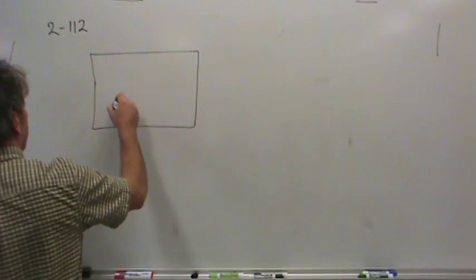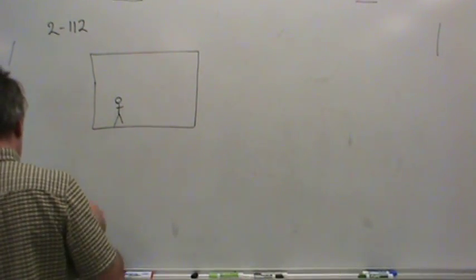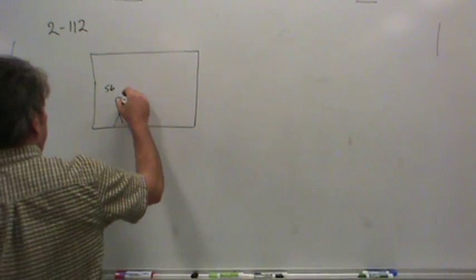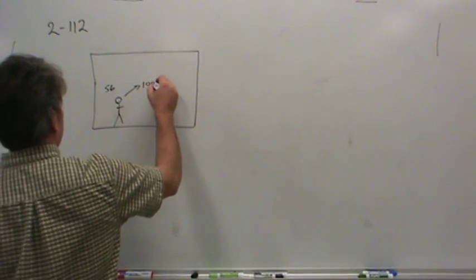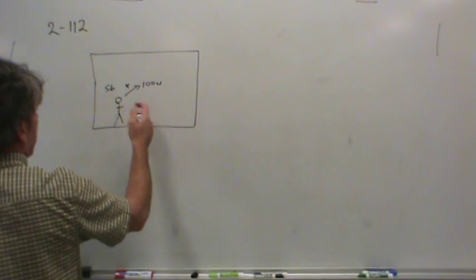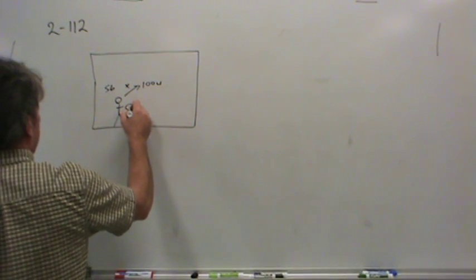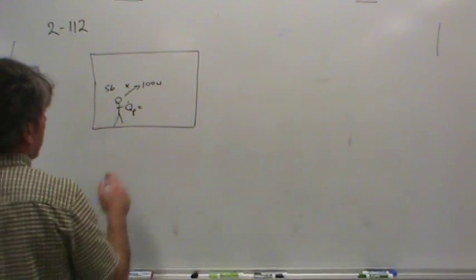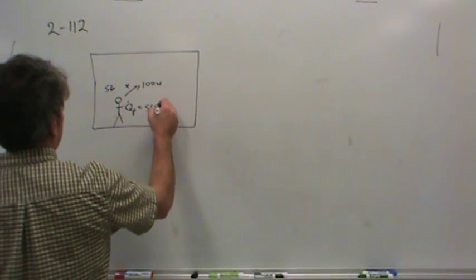We draw all the people as if they were one, and we know there are 56 people, and each person gives off 100 watts. So basically, 56 times 100 means that heat generation by people, Q dot P, would be 5,600 watts.